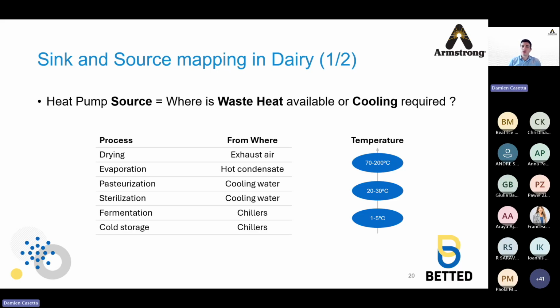So we've just talked about the heating and cooling side, and that comes with temperatures. Temperatures are driving the COP, so it's important now to take a closer look at which temperatures and which processes we have in the dairy sector. Let's start with the cold side, which is the source. So where is waste heat available, or where is cooling required? Well, we've summarized this into three buckets, basically.